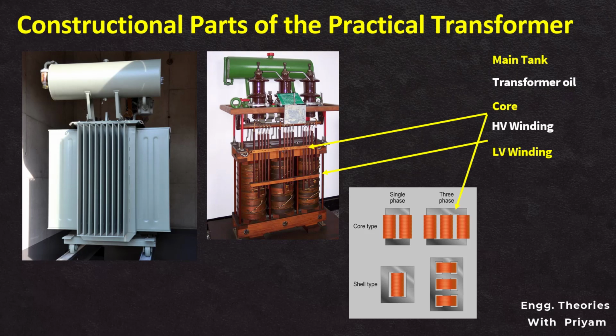The core is specially made of laminated steel and is responsible for creating a magnetic circuit. It enhances the efficiency of the transformer by facilitating the magnetic induction process. Winding consists of insulated copper or aluminum conductors and is crucial for carrying the electrical currents. There are two types of windings, primary winding and secondary winding. The primary winding is connected to the input voltage source, while the secondary winding is connected to the output. Based on the number of turns, they are either high voltage or low voltage winding. The winding in a transformer is also categorized based on the number of turns, determining whether it is a high voltage or HV winding and a low voltage or LV winding. For oil transformer, the whole setting or the core with the windings is immersed in oil.